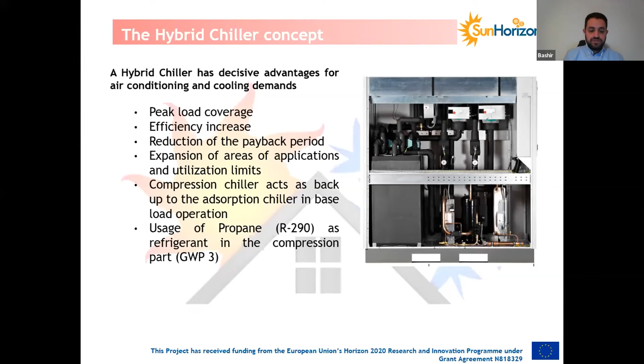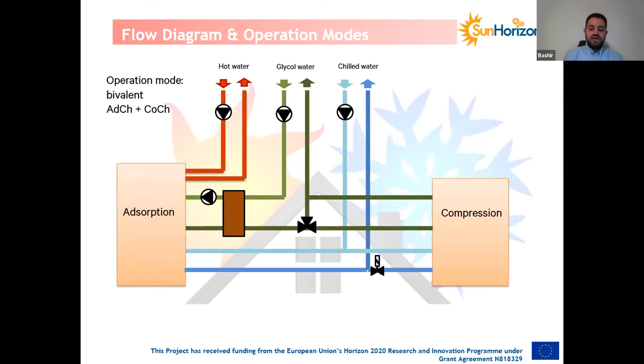There are three operation modes for the hybrid chiller. Either the adsorption is covering the whole load, which occurs mostly within the base load coverage mode, or the compression is functioning alone, which occurs mostly at night, for example, in solar cooling applications, or both systems, or both units, can operate at the same time in parallel to cover the whole cooling load at the highest outside temperature.